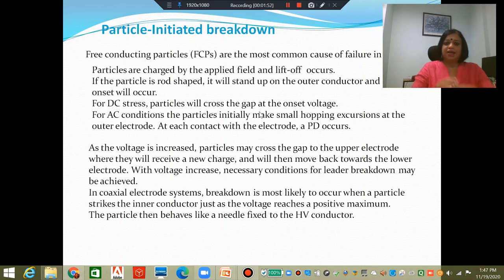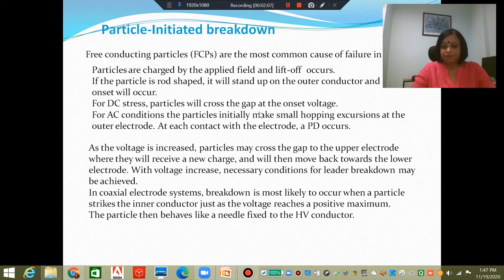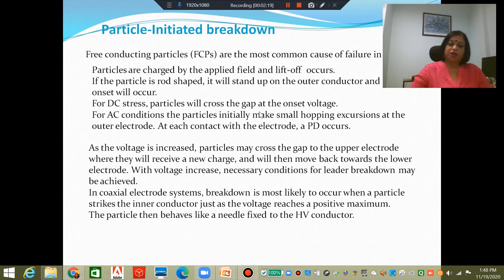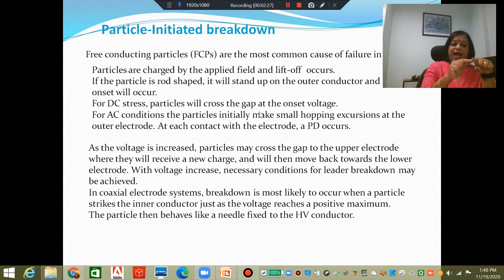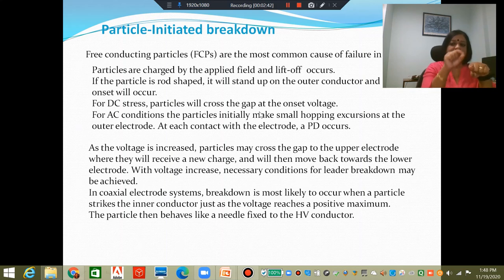If you have a DC stress, once these particles stand up, they will be accelerated in the direction of the field. When the voltage goes above the onset voltage, these particles will not only lift up — they will cross the gap and reach the inner conductor. With AC, the particle will lift up but before it can move very close to the inner conductor, it will drop off again as the voltage polarity changes, making small hopping excursions. Every time it comes back, it is charged, has a potential, and when the polarity changes it quickly drops due to gravity. When it drops, there is a potential difference between the grounded electrode and the particle, and as a result a partial discharge (PD) will occur.